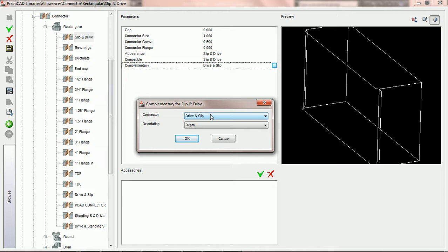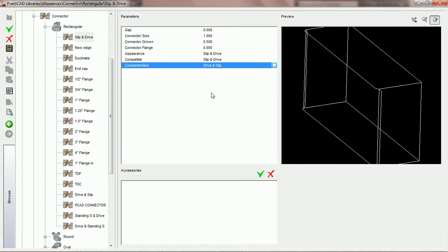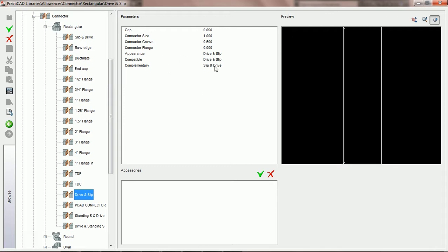Therefore, if you set a complementary connection for one connector, in this particular case, slip and drive is complementary with drive and slip, PractiCAD would automatically change and update the complementary connector for drive and slip to slip and drive. It just does the reverse. You don't have to change them both. You'll notice if we press OK, since we've set slip and drive to be complementary with drive and slip, if you click on drive and slip, you'll see complementary is now slip and drive. It does it automatically. You only have to change it once.